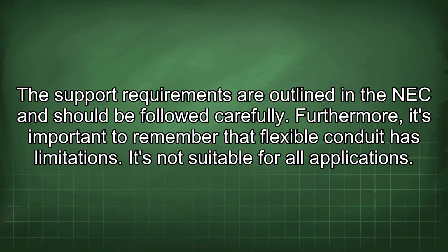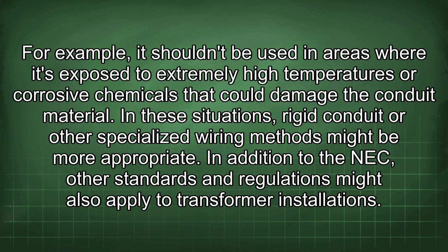Furthermore, it's important to remember that flexible conduit has limitations. It's not suitable for all applications. For example, it shouldn't be used in areas where it's exposed to extremely high temperatures or corrosive chemicals that could damage the conduit material. In these situations, rigid conduit or other specialized wiring methods might be more appropriate.